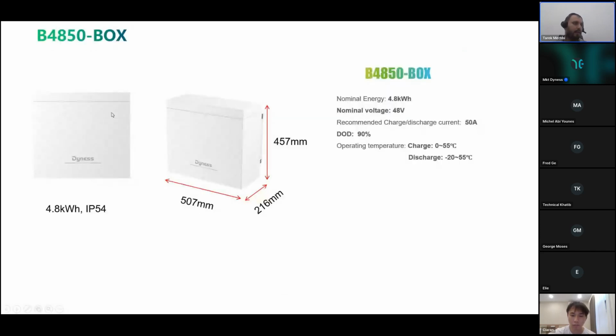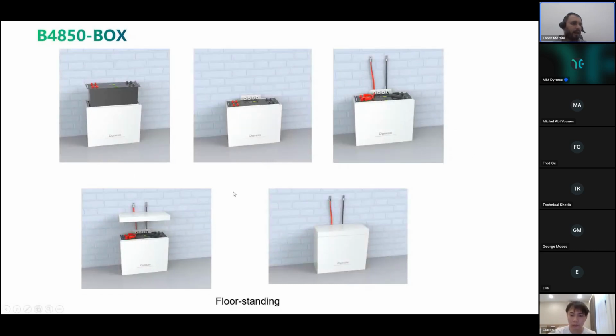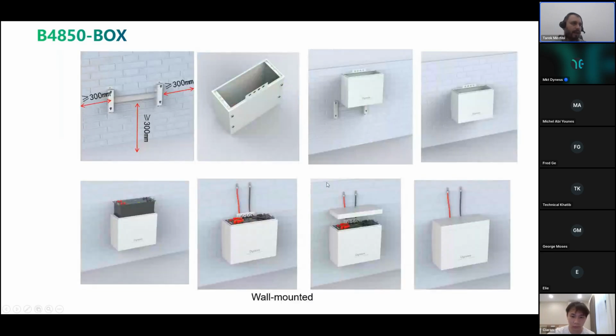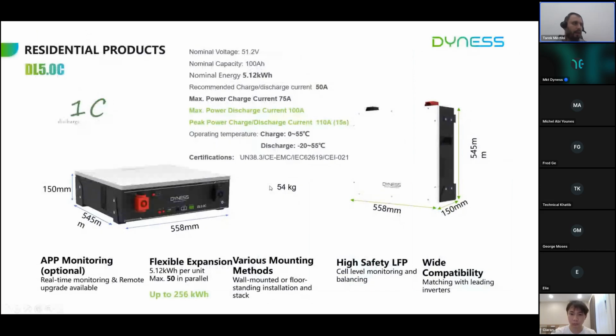Some mechanical or physical specification: it's around 50 centimeter and 45 centimeter length. Recommended charge and discharge current is 50 ampere. The installation can be floor standing, or it can be wall mounted. All the accessory is included in the box. And we can move now to a special product which is popular in Lebanon and the Middle East. It's the DL5.0C.